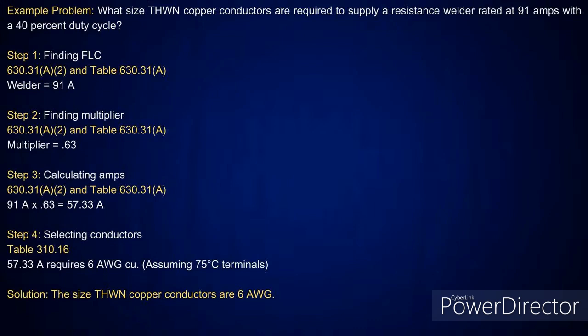Here's a resistance welder. Remember, I said when we get there, you want to look at table 630.31A. We got a 91 amp welder with a 40% duty cycle. Same calculation. 91 amps for a welder. Look at table 630.31A for 40% duty cycle. Come across, it tells you that multiplier is 0.63. Multiply that by 91 amps. That gives me 57.33 amps. Then step 4, go to table 310.16, pick up the 75-degree C column. The next size above that is 65 amps, which requires a number 6 conductor.